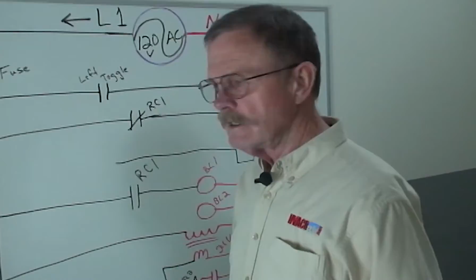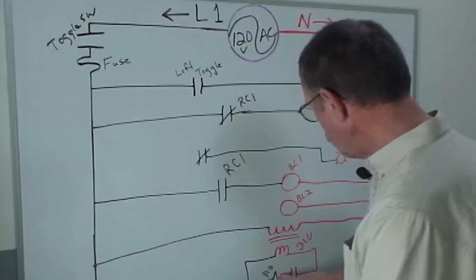We're going to go back here and make a little jog in our wiring diagram. No sense being neat about this - all you have to do is be able to understand your own drawings. That was a normally closed switch, and it was on relay 1, so we'll label it RC1. Where did it go from there? Back to L1. Circuit's done. So L1 comes in again, and we've chased out the normally closed circuit to a light.